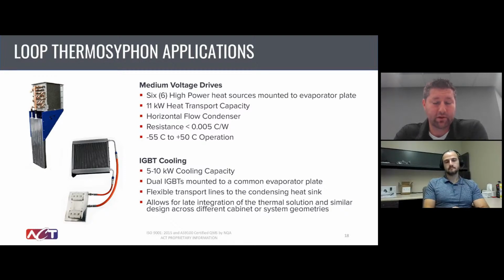This very similar design can be very flexible, so we can do it with a vertical airflow. We can also do it with a remote condenser with some flexible tubing. So again, a very flexible design as long as you have the condenser above your heat sources. In that exact example, you can see some of the figures there, it had an extremely low thermal resistance, so very low temperature gradient across those areas. And we were able to operate that system between -55 and +50 degrees C and transfer and reject over 11 kilowatts of heat. So a very capable solution in a fairly small form factor.